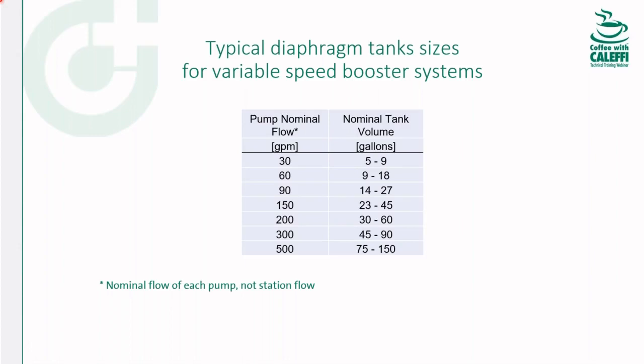Because again, that tank's purpose is to smooth out. What a diaphragm tank does is it makes a constant pressure variable speed booster more constant. Better constant pressure. And then it also allows for that low flow shutdown. It's not intended to keep a pump off all night long. It's intended to allow the pump to stop from time to time and stop using electricity and then restart when that flow is reintroduced. So that's the important part about tanks, and that's why the sizes don't need to be very big. You don't worry about starts per hour with a variable speed pump anymore.